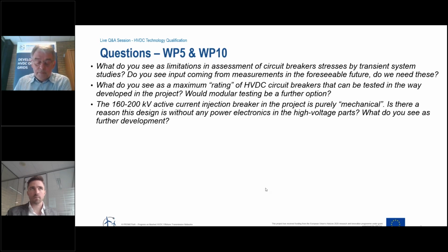So the question about the active current injection breaker. First of all, 160 to 200 is the testing voltage conducted at the KEMA laboratory using the double break modular type of DC circuit breaker. The mechanical HVDC circuit breaker with current injection can be expanded to the 525 to 600 kV level with a multi-break module with 4 to 6 units connected in series.